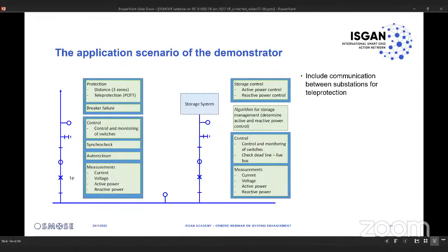The application scenario of the demonstrator is shown here. We assumed a small substation — the reason we started from a substation application is that this is where we already have many IEC 61850 devices available on the market. On the left side, we modeled one feeder with typical protection functions, breaker failure functions, control functions, synchro check, auto-reclosing, and measurements — a typical feeder as found in a transmission substation.